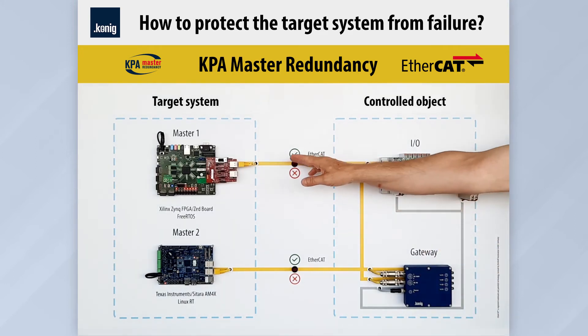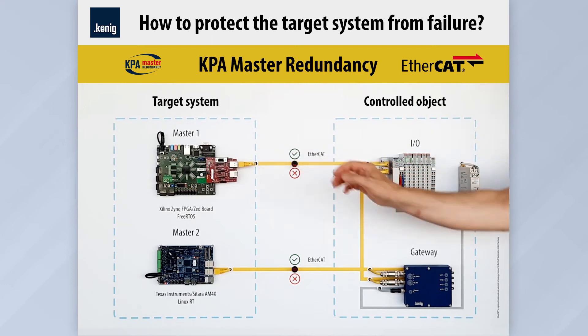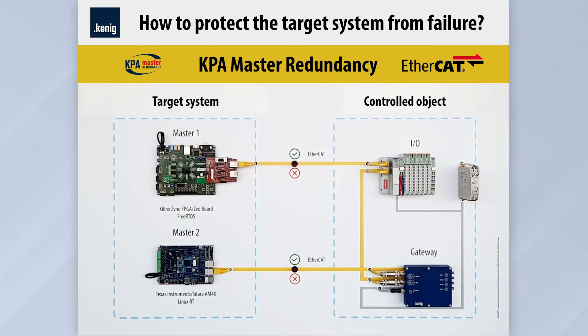By flipping the upper switch, a failure of the active master is simulated. If the next datagram consequently does not reach the passive master on time, the timer is triggered and the passive master takes over control. It starts to generate and send a new datagram to the network, with a delay equal to the watchdog timer and never exceeding one cycle.